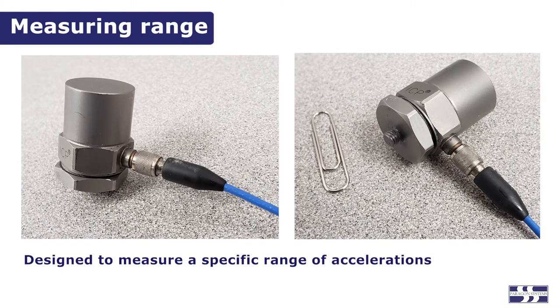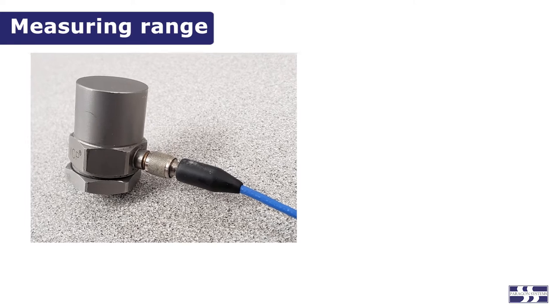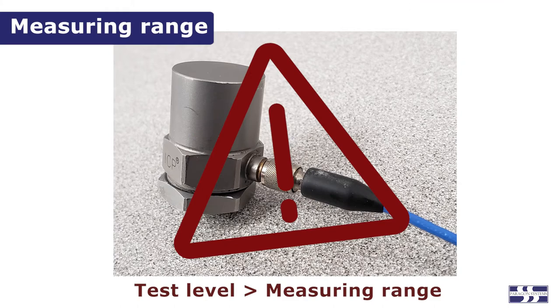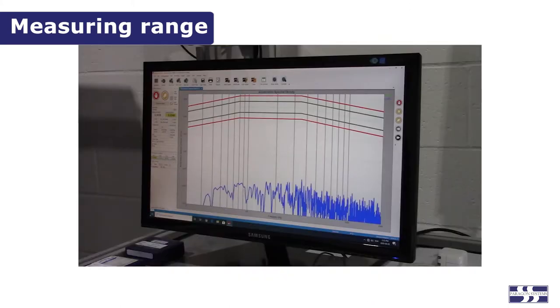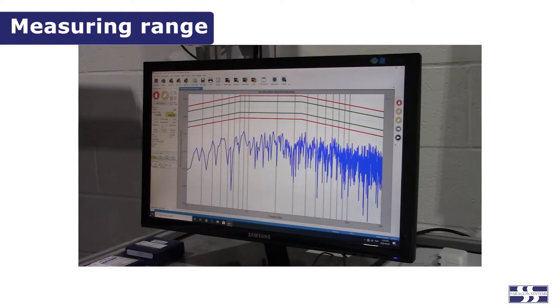Accelerometers are designed to measure a specific range of accelerations. Because of this, two things should be considered when selecting the appropriate one. An accelerometer can be permanently damaged if the test level exceeds the maximum measuring range. This can be prevented by using an accelerometer with a larger measuring range.